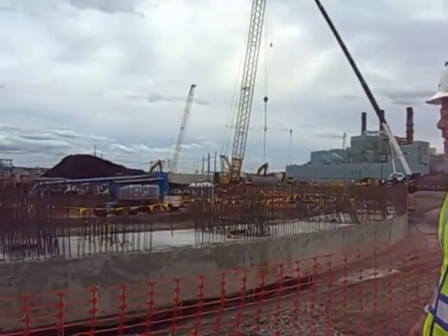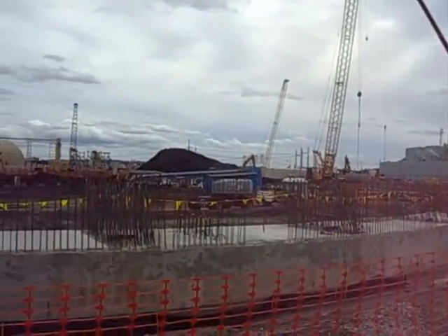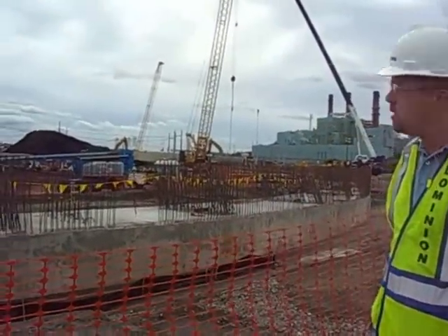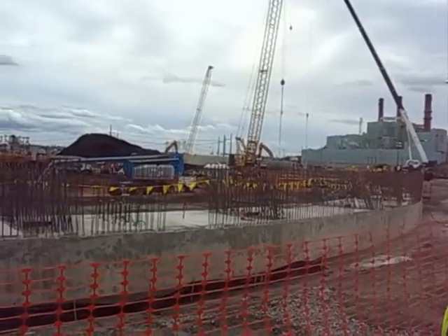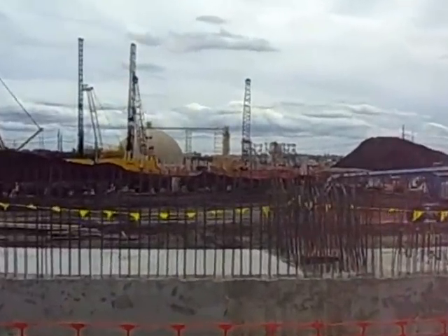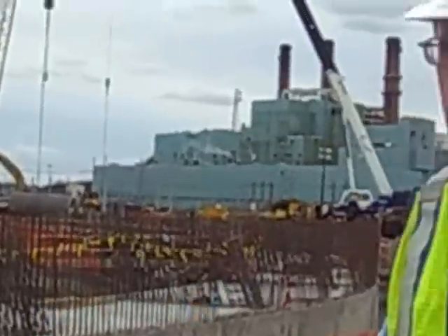The activities in the background — they're backfilling all the excavations, covering up that piping, and getting ready to essentially pour the floor of the cooling tower basin. The basin is about 400 feet in diameter. There are 44 meridional columns that run around this that hold up the shell itself. The shell is 497 feet high from grade.